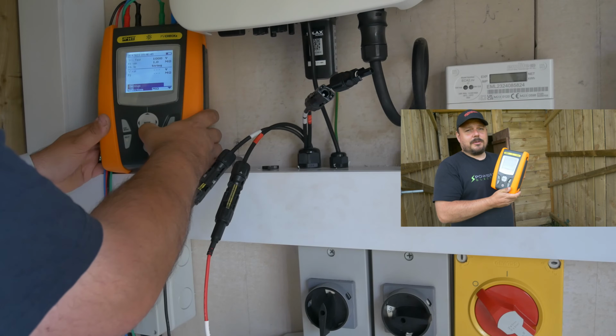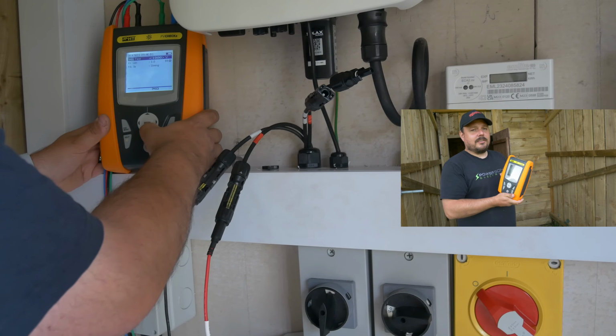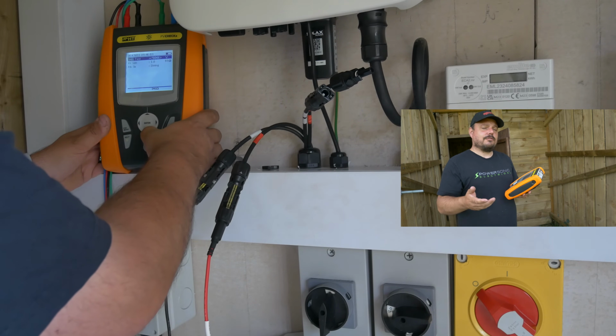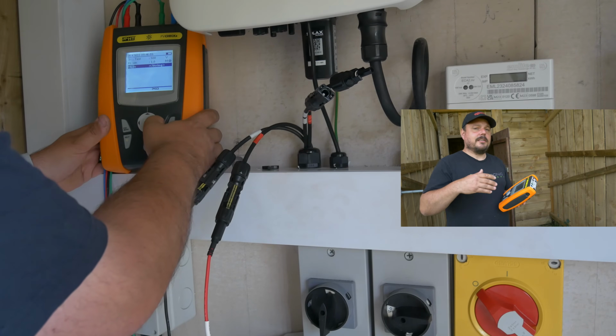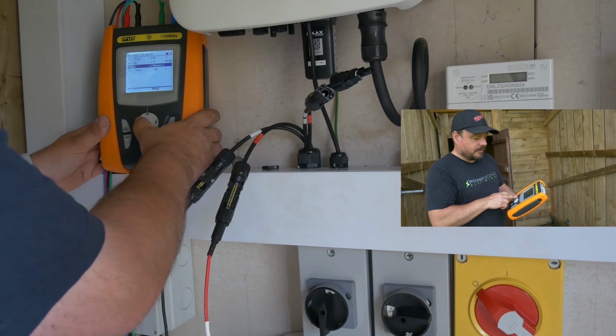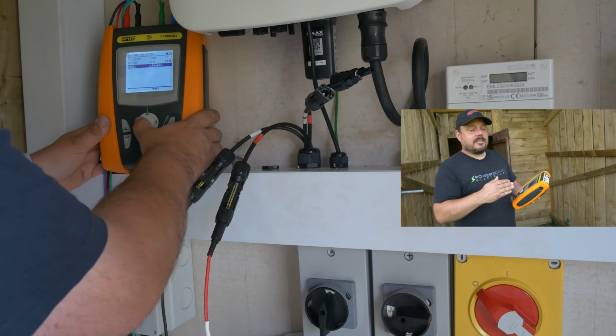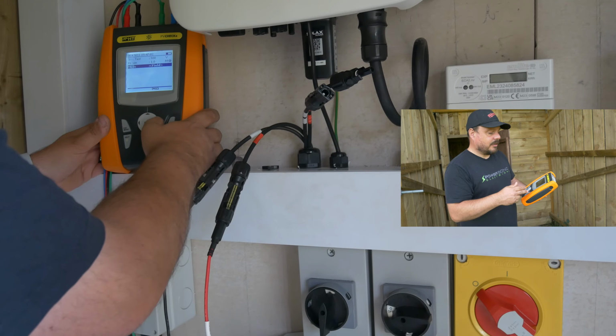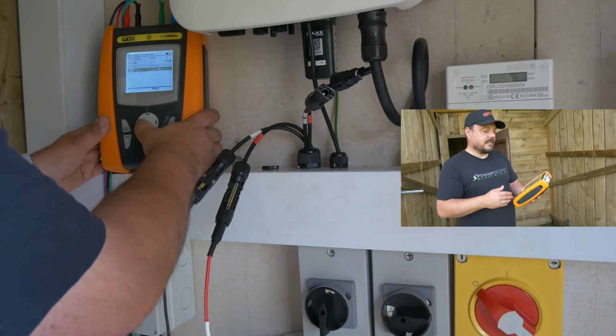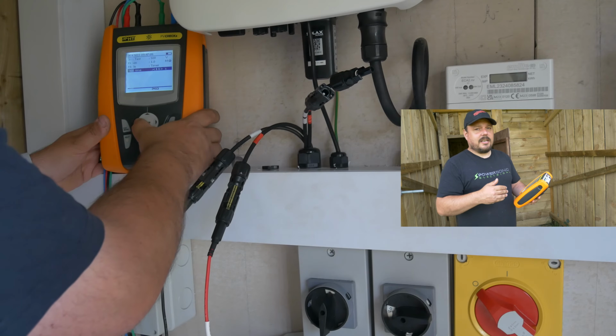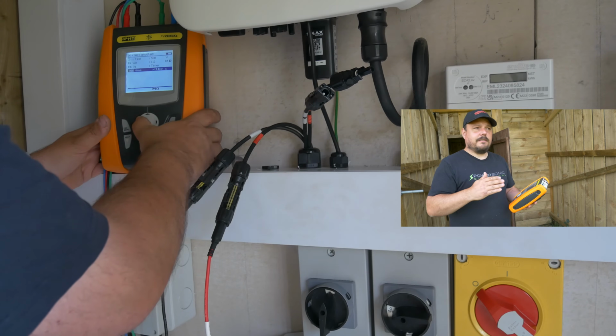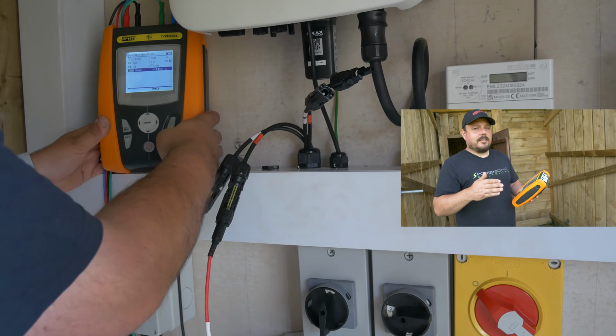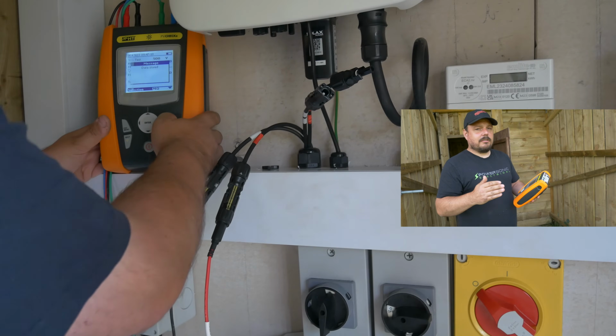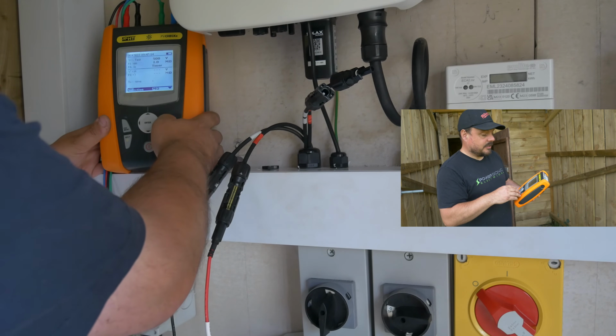It does it all in one simple test, and then it will output that in a certificate format should you wish, or electronically for you to review and amend into your documentation later on. And on top of that, it has the other tests separately as well, so you can still do your earth continuity test as a separate test. You can do your insulation resistance test. This doesn't go as far as the 1500 volts. So I think you need to be mindful of that. If you have got larger arrays, that's where the IsoTest comes into its own.